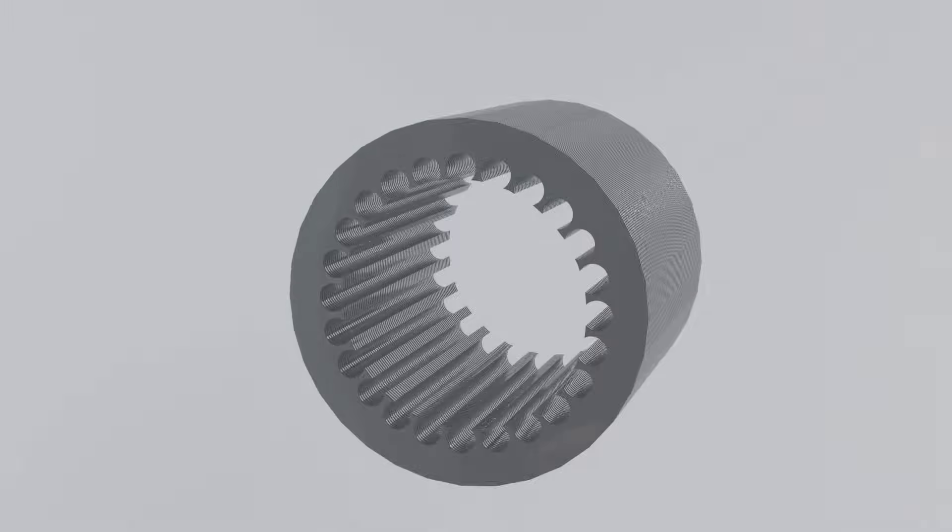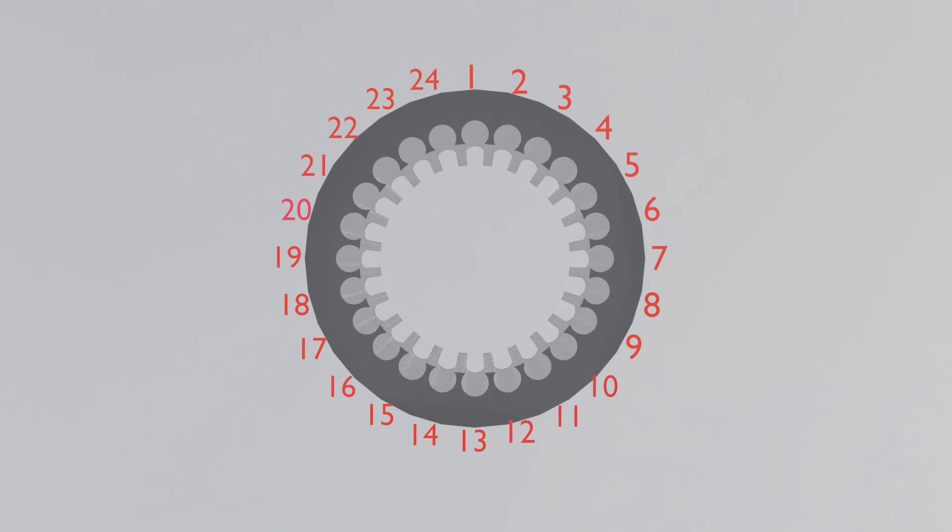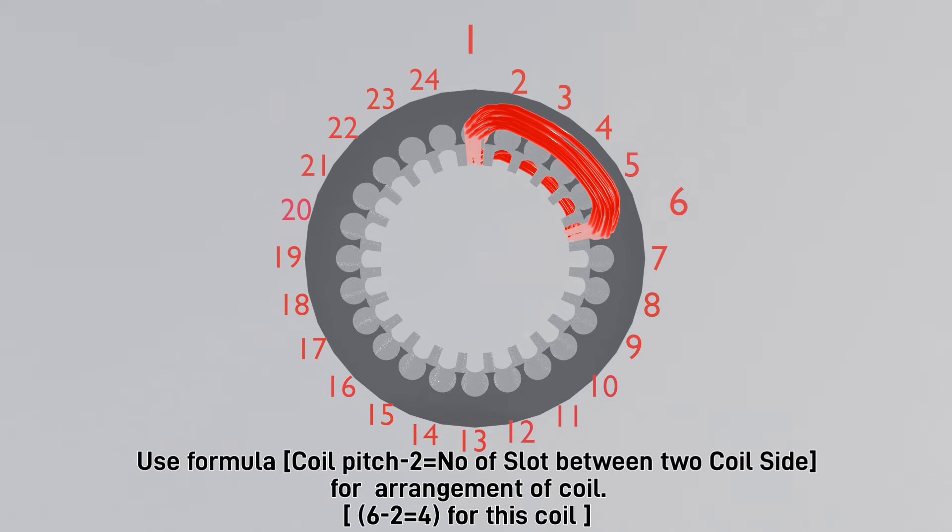Let's insert the winding in the stator core. We insert the first coil of R phase in slots. You see that one side of the coil is in slot 1, and the other side of the coil is in slot 6, because the coil pitch is 6 for this winding.